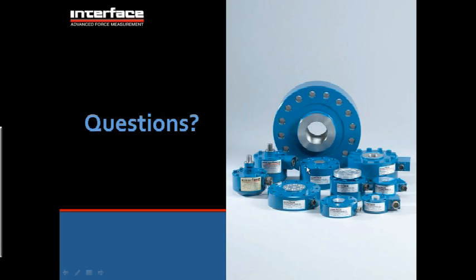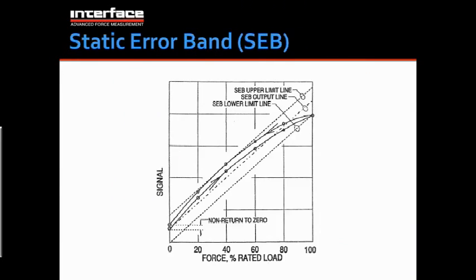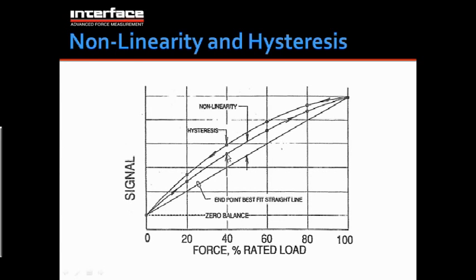Let me go back to that slide. So here it is. Yeah, so hysteresis is measured at the 40% on the ascending and descending calibration procedure. And it can be done at 50. In this case, it's shown at 40 because this graph is showing the standard calibration procedure, which consists of 5 points up and 1 point down. When we have calibration runs with more than 5 points, we take a measurement reading at 50, and on the way down we do that 50% measurement again, and the hysteresis will be determined at the 50% range. On the calibration, right? Correct.